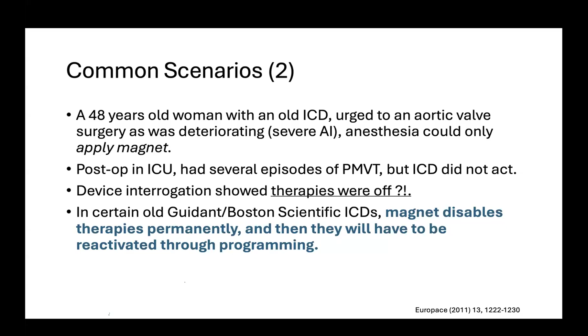The patient had several episodes of polymorphic VT, and the ICD unfortunately did not act on these events. When the device was interrogated, it did show that the therapies were off, although the magnet typically does not permanently disable the device therapies. However, in some certain older Boston Scientific ICDs, it does this until it's reactivated through programming. So something to keep in mind. We don't see this every day or most of the time, but just to keep in mind to check this.